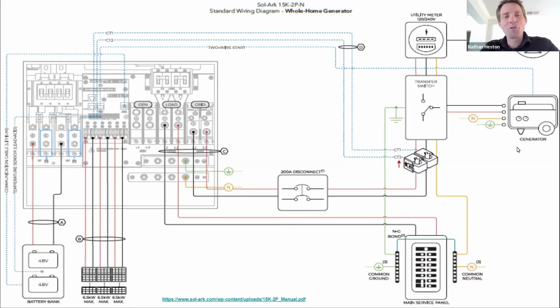That's exactly what I was going to ask you. I mean, when we would do a system like this with a generator connected, you've got solar power producing at the same time. We would use a lockout module or something so we don't fry the generator. But you're saying that the Sol-Ark is smart enough to realize the difference and prevent that with the software. It is, but there are exceptions.